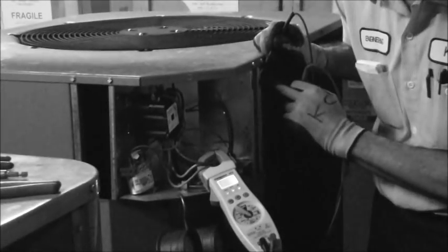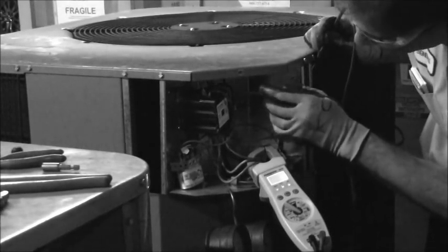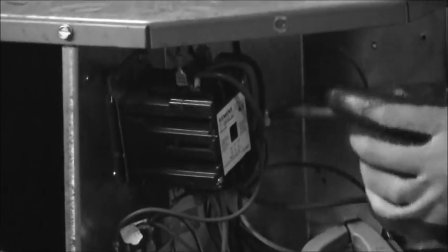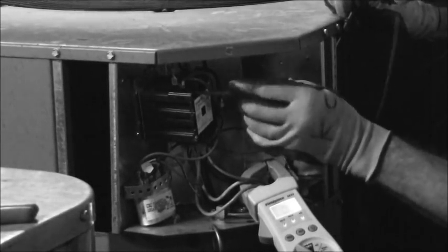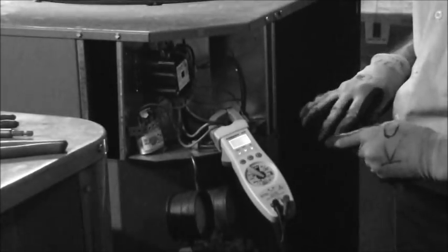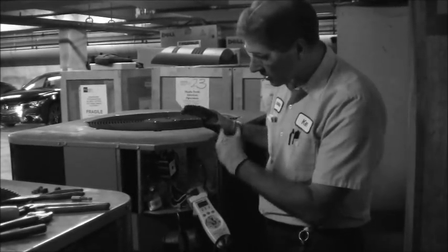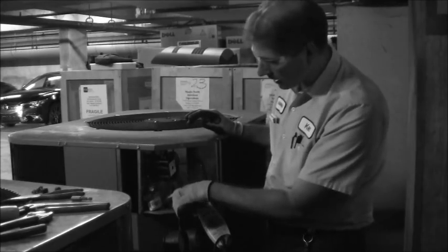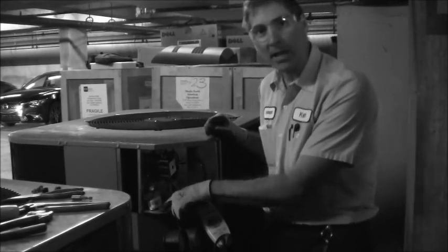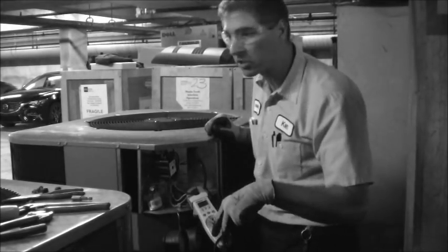I'm going to maintain my right hand on that ground source, taking my left hand, and now I'm going to touch the 3 phases of the top of the contactor, A, B, and C. So here's phase A. It's all good. You know what? One thing that I should mention, that I did earlier and forgot to mention: before I even touch that, there's a capacitor right here. A capacitor is the one component that can store electricity and it can still kill you.